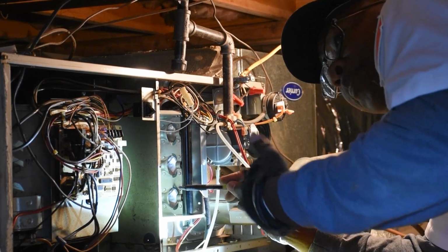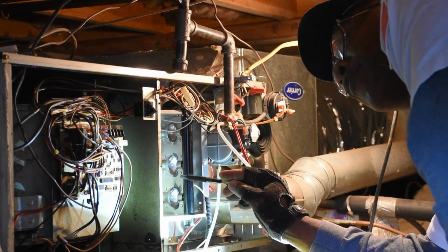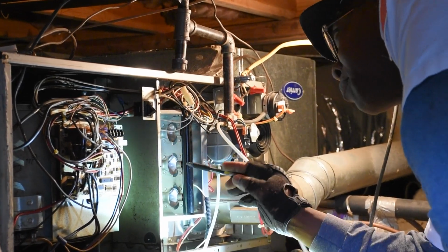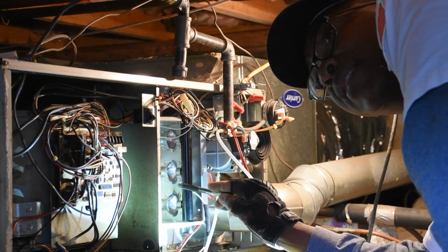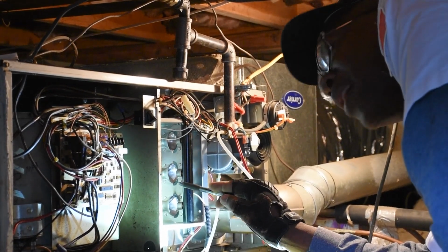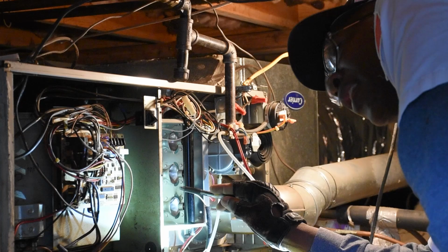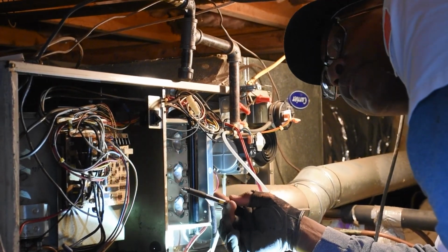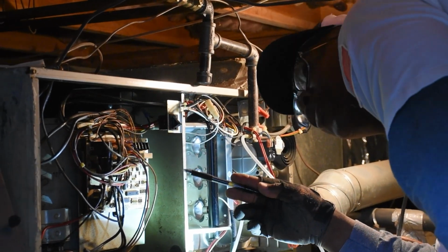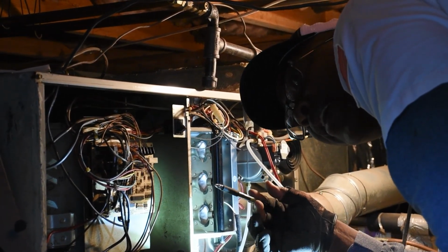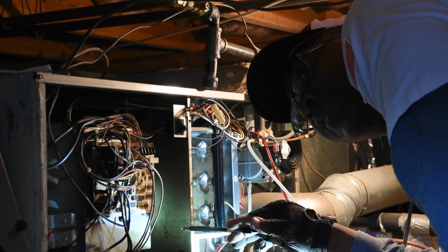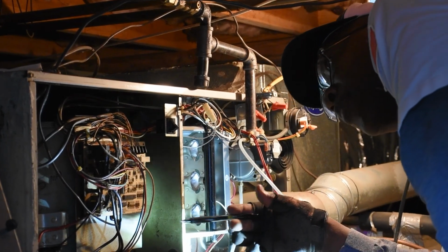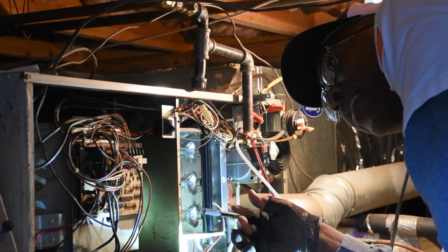And the process just pretty much continues at that point. Now, if for some reason one of the orifices was blocked up or the burners had a crossover that wasn't completely cleared and the flame didn't make it all the way to the end, the flame sensor would not detect a flame, and in that sense, it would activate a safety shutdown and tell the control that, okay, something is not right. And the control pretty much would shut the process down. And then you would get a trouble code, and obviously a tech would have to come out and figure out why that was not the case.